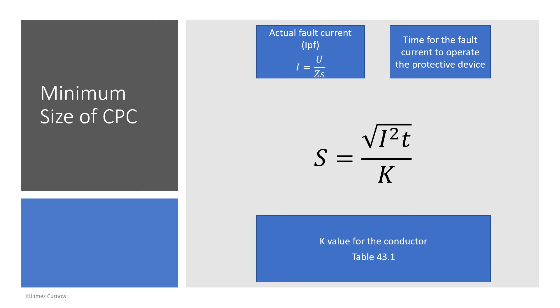The second adiabatic equation is for the minimum size of CPC. That is S equals the square root of I squared multiplied by T divided by K. In this equation we're talking about fault current which is always live to earth. To find the current I we divide the voltage by the Zs, which can be measured or calculated, and that gives us the actual fault current.